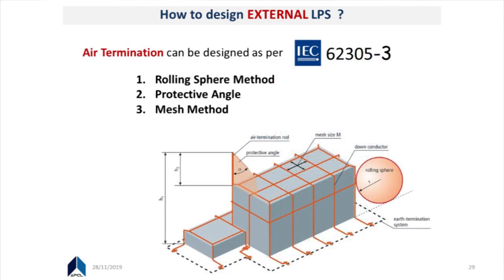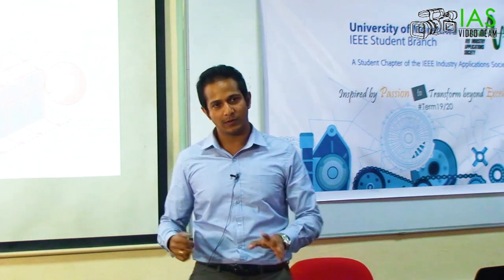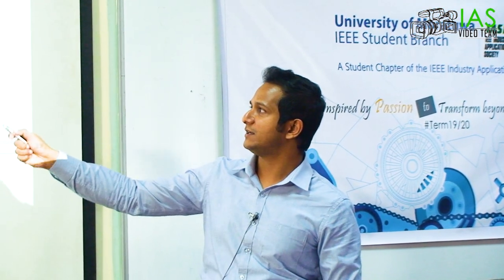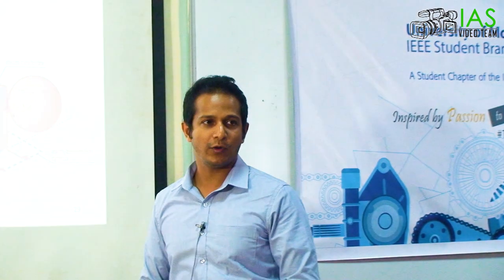So our air termination should be, I'm mentioning should because we are following 62305, but as an independent engineer I should say that I cannot stress anybody to follow French standards or IEEE standards, but you can design with 62305. So it gives 3 basic design methods for air termination systems.